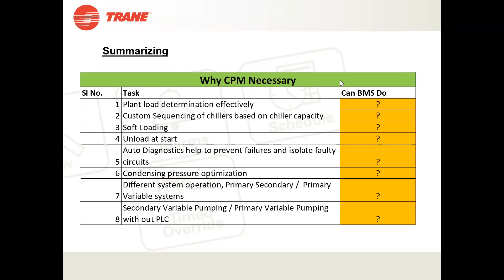Did I answer your question, Mr. Chakraborty? Yeah, Mr. Jilani, I was just curious whether this logic is already built into the system, or if you do a local logic for the CPM. No, it is inbuilt logic, Mr. Chakraborty. It was introduced in the 90s, and from there onwards there was continuous development, with continuous patches and upgrades available in the chiller plant manager. All the features discussed come as a pre-programmed solution in our master controller. So for the commissioning engineer, it's just about enabling that and putting in the customer's customized set points, and the system is ready to operate without any errors.